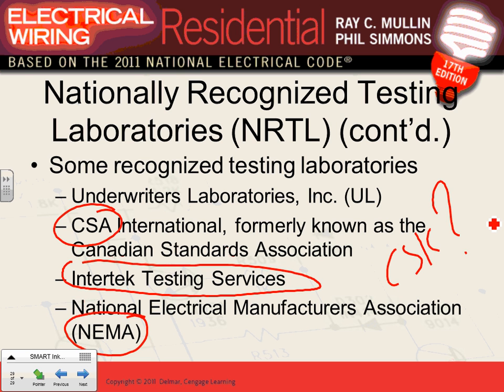Any comments, guys? Any questions about this? So to summarize, as I said: safety starts with safe equipment, UL. Then you design it and install it based on the NEC code book—that's safe equipment design and installation. Then you work on the equipment safely based on 70E, that's for arc flash and blast and all that stuff. Then you maintain the equipment based on 70B. Then you're done—then you're electrically safe. You have an electrically safe system.